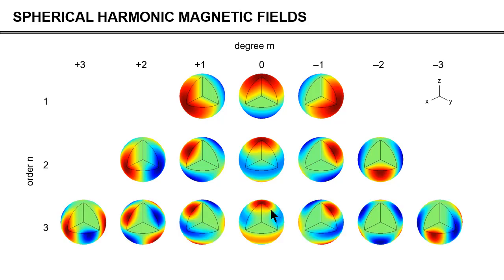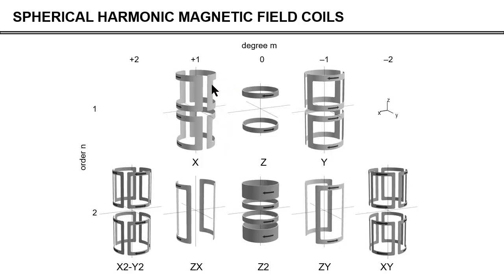You can also have five second-order spherical harmonic fields, seven third order, nine fourth order, et cetera. Of course, the more you have, the better you can approximate your inhomogeneity. However, in reality most MR scanners only have first and second order spherical harmonics, so you cannot expect to perfectly cancel your inhomogeneity. The nice thing about spherical harmonic functions is that they can actually be generated inside the magnet with specific coils designed to generate those functions inside the bore of your magnet. So your MR scanner has X, Y, Z gradients, but there will be at least five additional coils generating the second order magnetic fields.